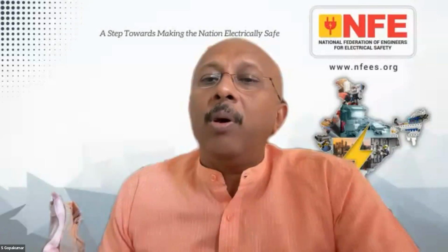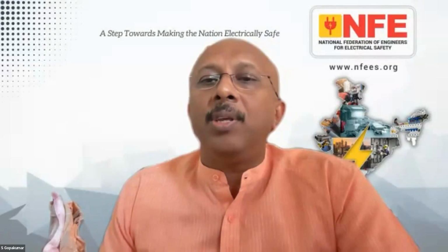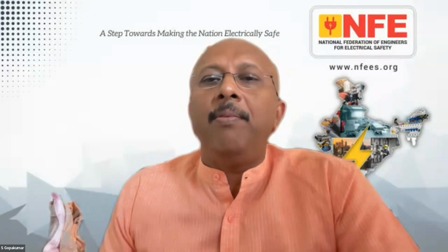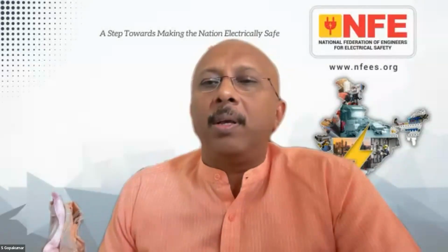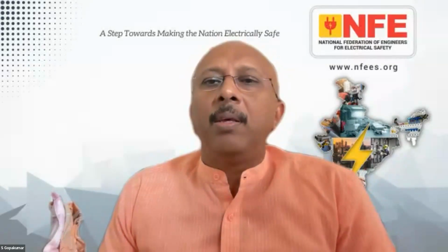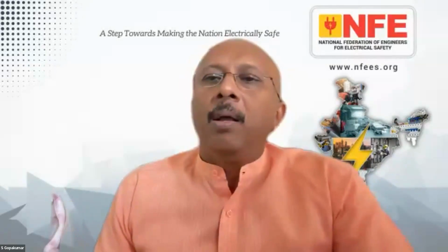What about a 0 volt requirement between neutral and earth? Okay, Mr. Imran, this is already addressed. There is nothing like 0 volt between neutral and earth. It can be even 230 volt, and not only the lift, every electronic item is supposed to work even with 230 volt between neutral and earth in case of an IT system. Generally, this is a misnomer. People think that if the neutral to earth voltage is low, the earthing is good. This is the thought behind it generally among people. So this we need to address.